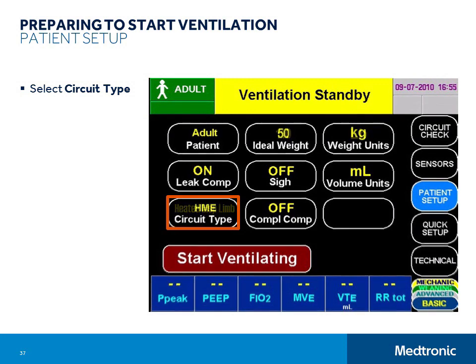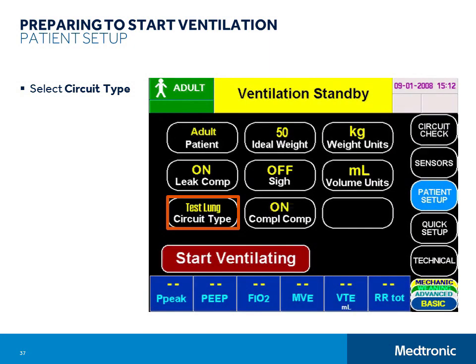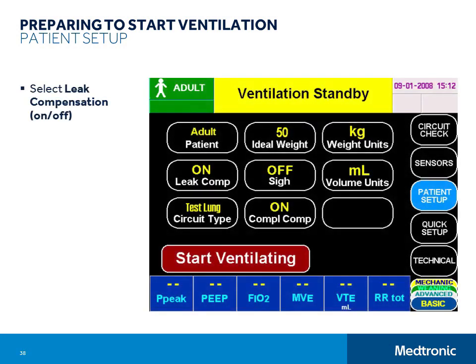The next setting is leak compensation. It can be set to on or off. We recommend that you always keep leak compensation turned on. When leak compensation is on, the e360 automatically adjusts the leak compensating bias flow between 3 and 8 liters per minute for ped infant patient selection and between 3 and 15 liters per minute for the adult patient selection in order to maintain an end expiratory base flow of 3 liters per minute.